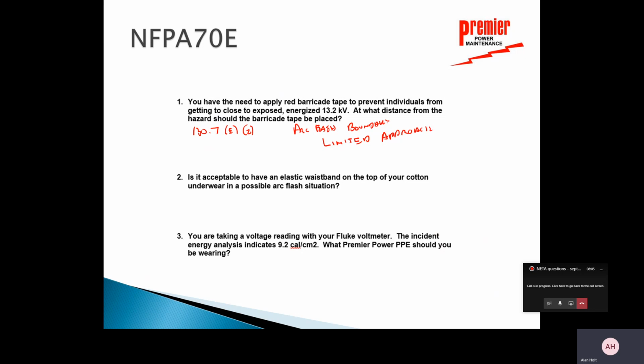So I've heard people say it just needs to be 6 foot out there. That's not necessarily the case. 6 foot will cover that limited approach boundary for 13 kV, but it may not cover the arc flash boundary. So we want to make sure that people are outside that arc flash boundary as well.